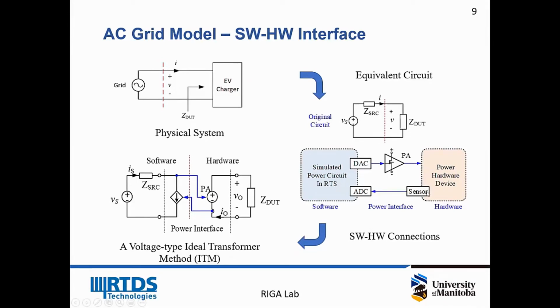And also there is a feedback. It sends the grid current from the hardware, and then there is an analog to digital converter to put this current signal into the software. We also can use a voltage type ideal transformer method, ITM, to represent the system here. Inside the software, there is a voltage source and an impedance. And the software provides the grid voltage signal through the amplifier and then provides it to the hardware. And then you also can see that we sense the current and feed it back to the software. And inside the software, there will be a voltage controlled current source to represent the EV charger.